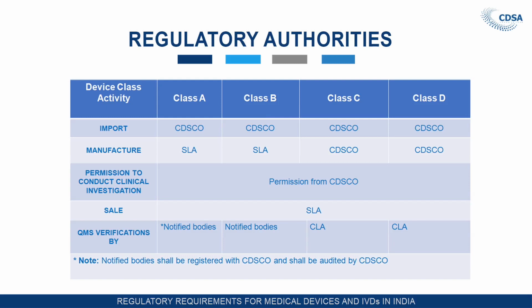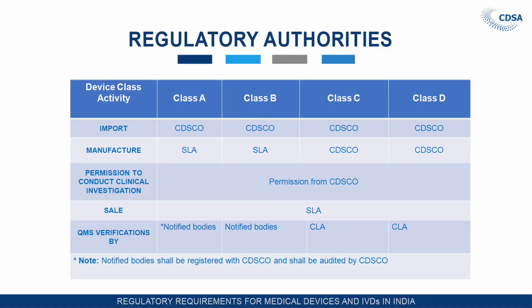QMS verification: we have discussed that there is a role of the notified body. The notified body will be responsible for QMS inspection of class A and class B devices, and based on the audit report of the notified body, the state licensing authority will grant the license to class A and class B manufacturers if the documents and report are found satisfactory. For class C and class D devices, the central licensing authority is responsible. They will audit the manufacturing premises with respect to the quality management system, and after receiving the satisfactory inspection report of the QMS as well as the technical documents as required in the Medical Device Rules 2017, they will grant the manufacturing license to class C and class D manufacturers.